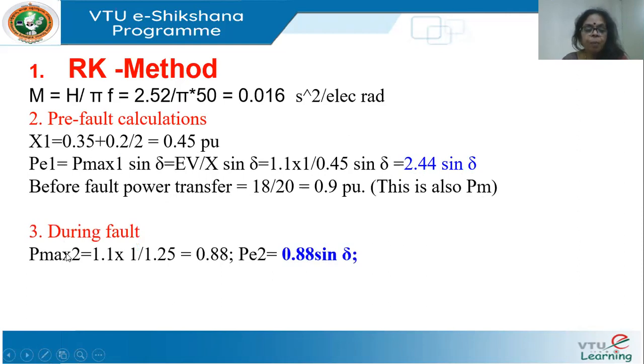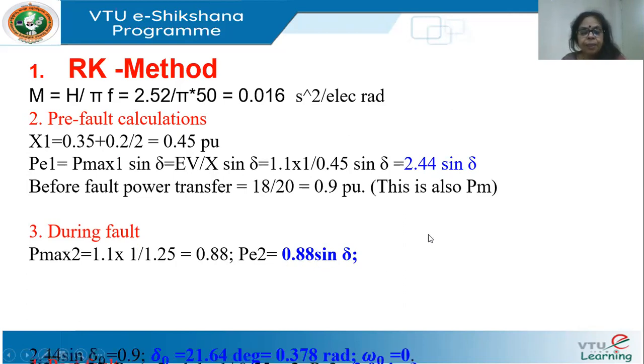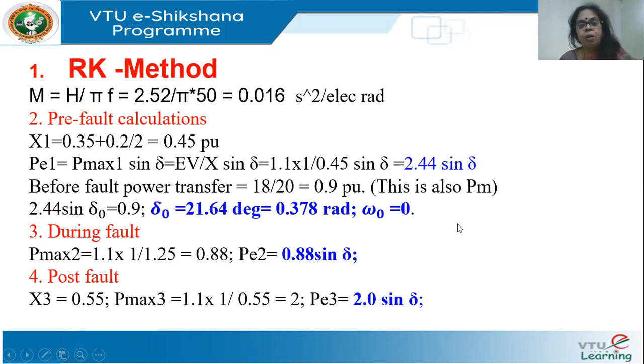During the fault, P_max is 1.1 × (1/1.25) = 0.88. The 1.25 is the reactance when you short the middle of one of the lines — you find the transfer impedance, which works out to 0.88. So the expression for P during fault is 0.88 sin δ. The initial value δ₀ is found by equating 2.44 sin δ = 0.9, giving δ₀ = 0.378 radians, and ω₀ = 0.